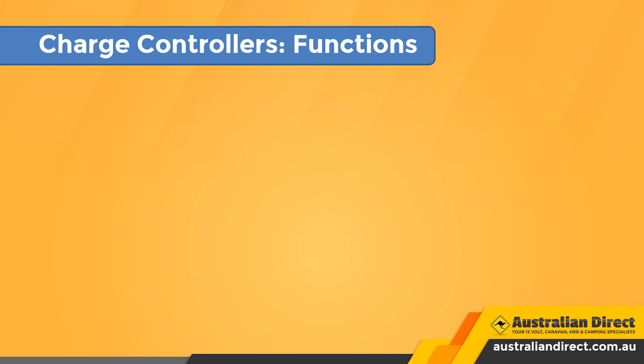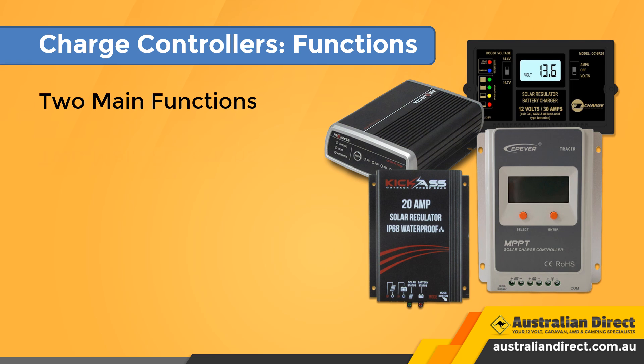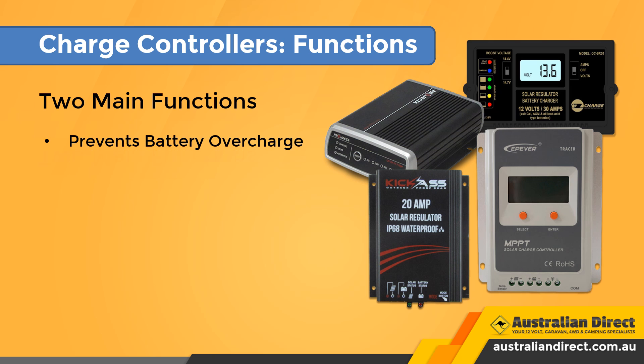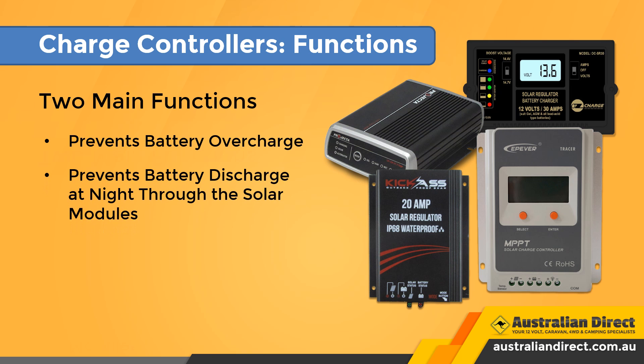A charge controller is an important component in a battery-based system. They're not used in straight grid-tie systems as they don't have batteries to charge. Their primary role is to manage charging the battery bank — it prevents it from overcharging, and many of them control the current and voltage at which it charges. At night, the voltage of the battery bank is higher than that of the array it's connected to. Without a charge controller, the tendency would be for voltage to flow out of the battery bank. A charge controller prevents that, allowing flow to only go one way — into the batteries.